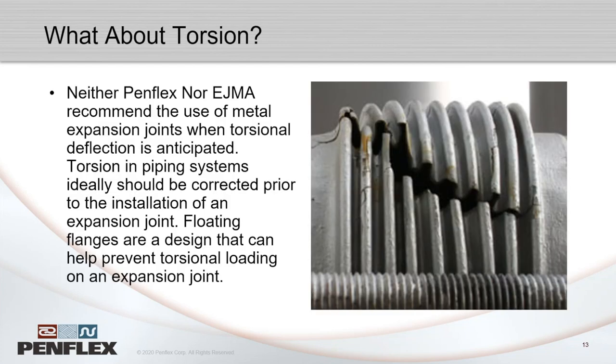What a bellows cannot accommodate is torsion. Neither Penflex nor EJMA recommend it, because torsion puts a lot of shear stress on the material and the bellows would fail very quickly. Torsion is usually caused when pipe fitters torque two fixed, misaligned flanges into place. One way to help is using a floating flange on one end — the same problem exists with metal hose. But torsional issues really need to be solved before an expansion joint is introduced; an expansion joint will not solve them.